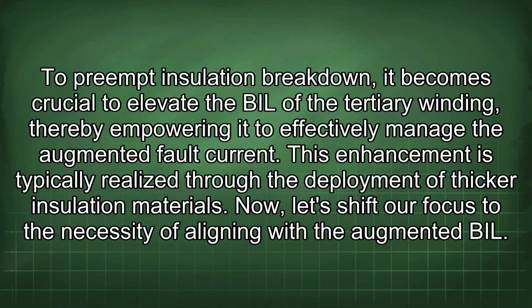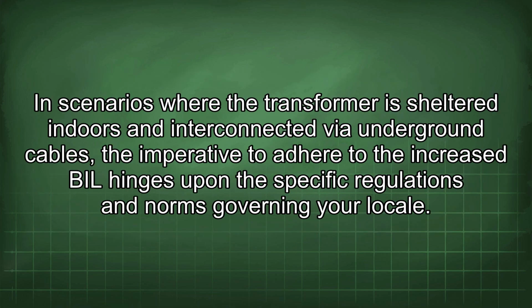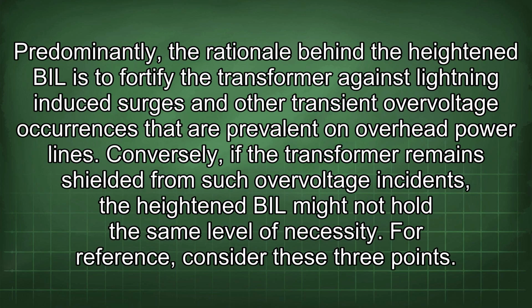This enhancement is typically realized through the deployment of thicker insulation materials. Now, let's shift our focus to the necessity of aligning with the augmented BIL. In scenarios where the transformer is sheltered indoors and interconnected via underground cables, the imperative to adhere to the increased BIL hinges upon the specific regulations and norms governing your locale. Predominantly, the rationale behind the heightened BIL is to fortify the transformer against lightning-induced surges and other transient overvoltage occurrences that are prevalent on overhead power lines.